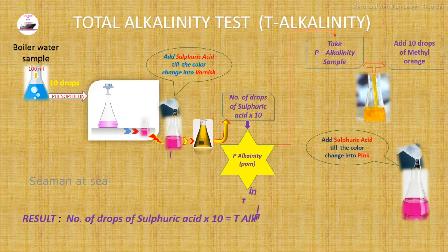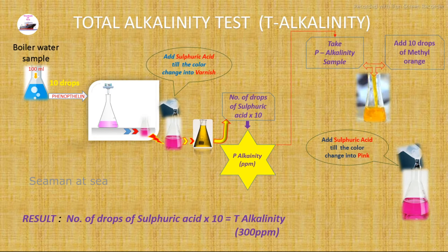The quantity of sulfuric acid added gives us the total alkalinity level in the boiler water. The number of drops of sulfuric acid multiplied by 10 gives the total alkalinity — 300 ppm is accepted by every surveyor. This test is used to find out the hydroxide, carbonate, and bicarbonate levels in the boiler water.